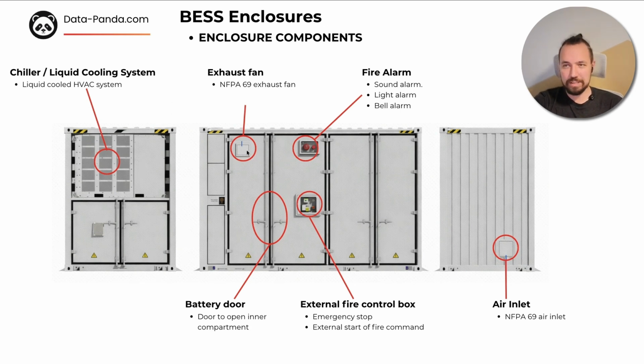Next, exhaust system, exhaust fan, and it will be NFPA 69 compliant. We'll talk about fire safety in our hot topics because it's very important. But for now, we need to understand that we have this emergency exhaust fan. It's designed for rapid removal of flammable and toxic gases, such as hydrogen and carbon monoxide, in case of a thermal runaway event. So if anything goes bad in the battery and there is a fire, it should remove these gases. So it's gas management, not fire suppression. And it's a key safety layer of a modern battery energy storage system. And as I mentioned, it's a requirement of NFPA 69 compliance.